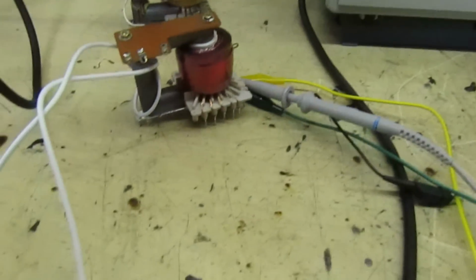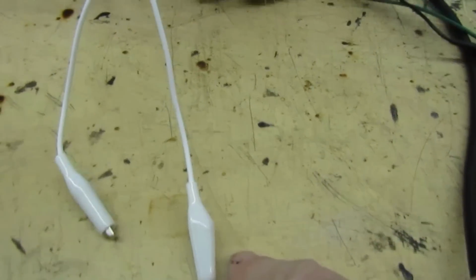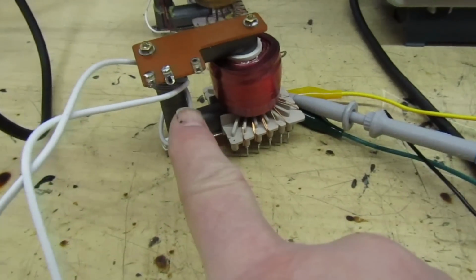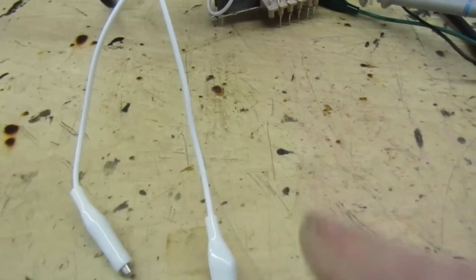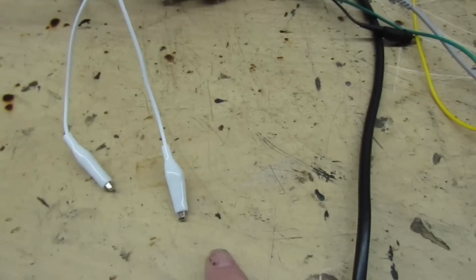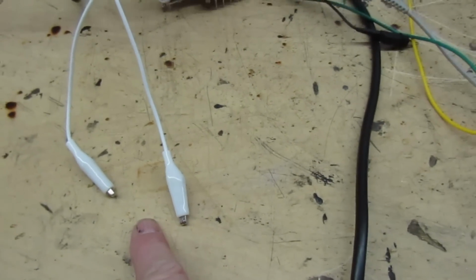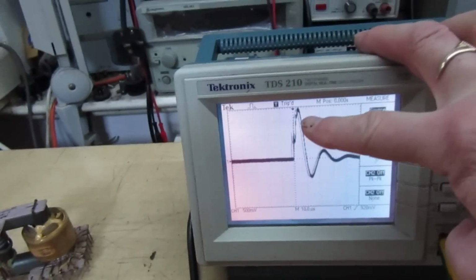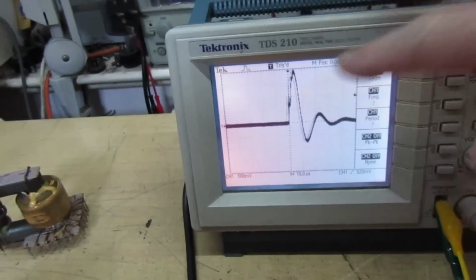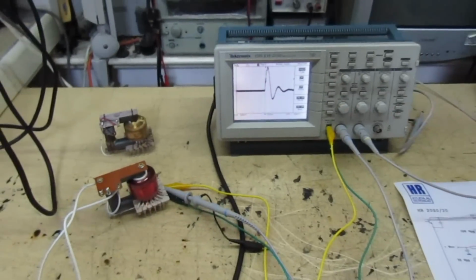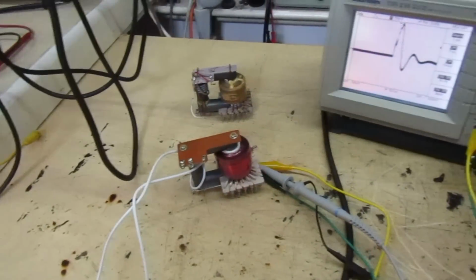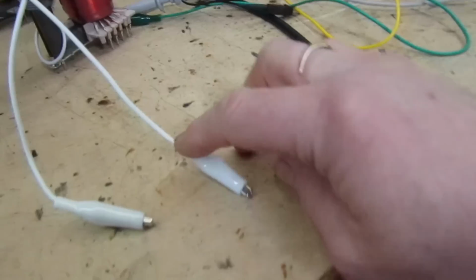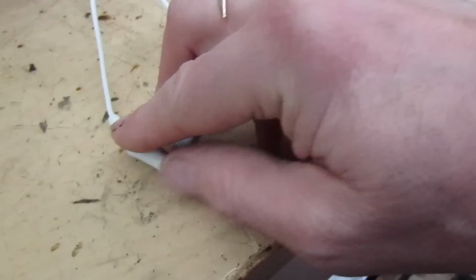Now what you do is take one shorted turn and wrap it round the limb of the transformer like that. If this transformer's good, when we touch these together it damps the winding and the amplitude should fall. I'm going to have to see if I can hold the camera at the same time, touching these crocodiles together.